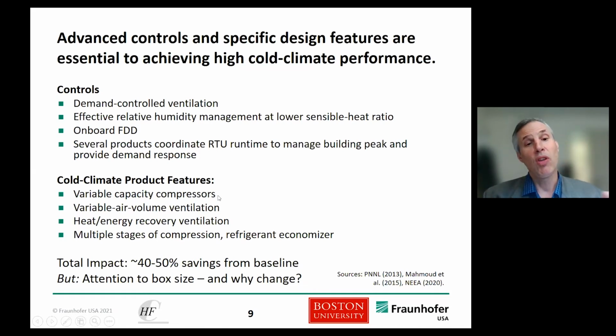People can do parallel stages of compression, multiple stages of compression. They can do things around variable air volume and heat recovery ventilation. These can dramatically improve the efficiency of these products and also improve their capacities at lower outdoor temperatures. But again, if you're doing all this inside this unit, you have to be really careful. This box size is reasonably fixed, and you can't change it too much, or you're going to be getting into some major work as part of a retrofit in terms of changing what's going on the roof of the building.